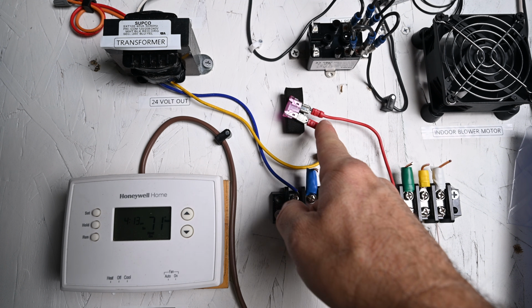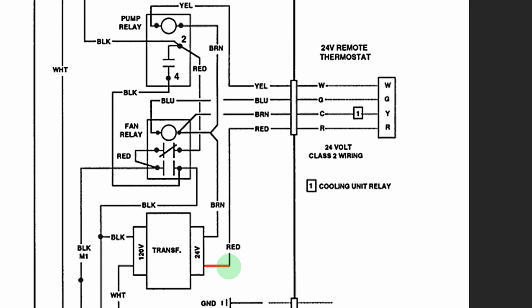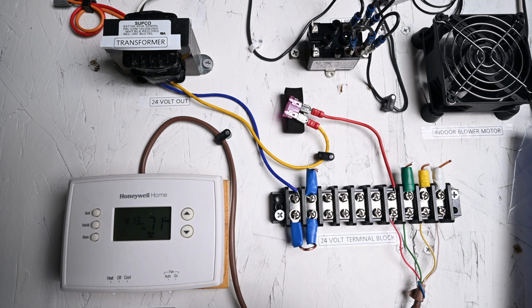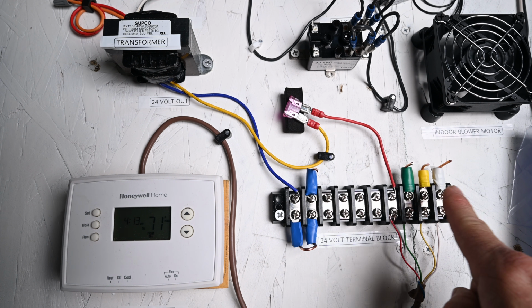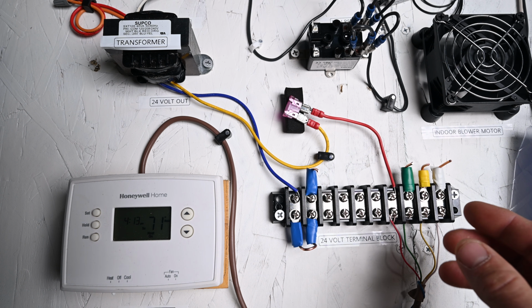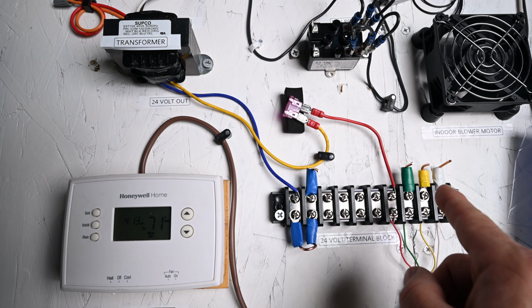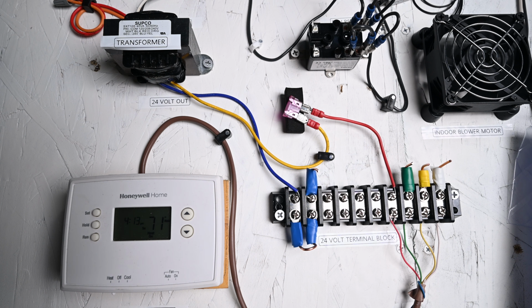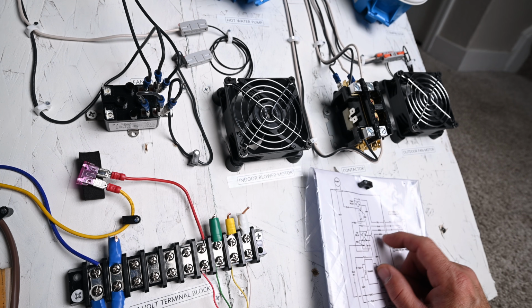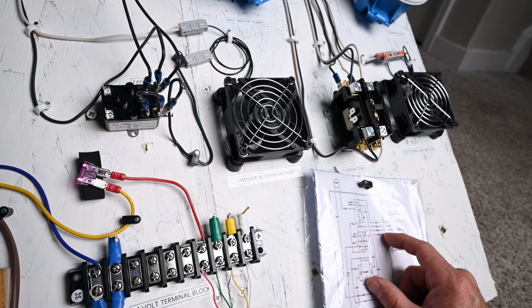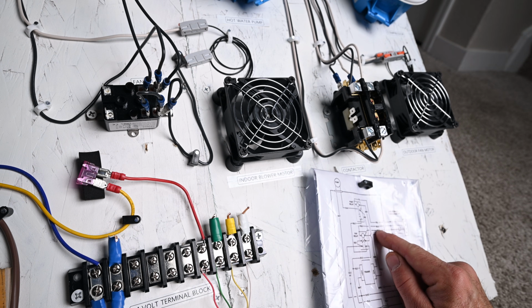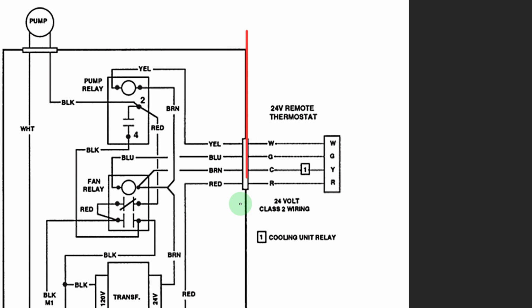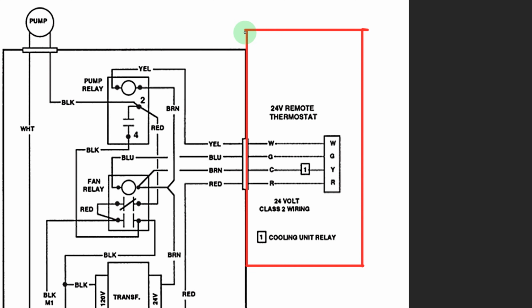Our main power wire, the low voltage power wire, comes into the terminal block, goes into the thermostat wire, into the thermostat. Now, none of these can be energized. We could jump it out, but none of these will be energized until the thermostat tells it to energize. So let's see this in action. Don't pay attention to the colors past this block because they're going to be wrong. We're not worried about the colors, we're worried about the wires.